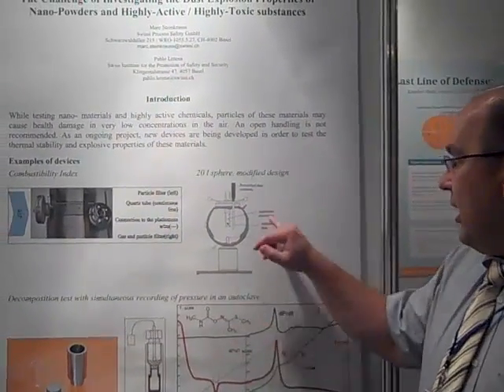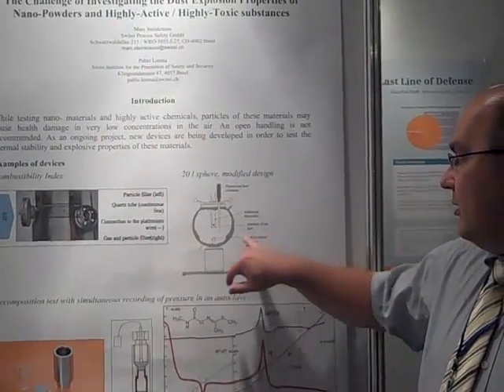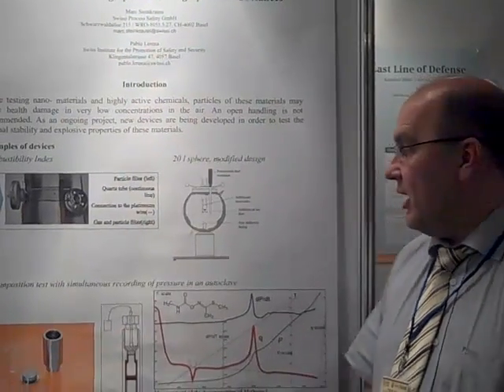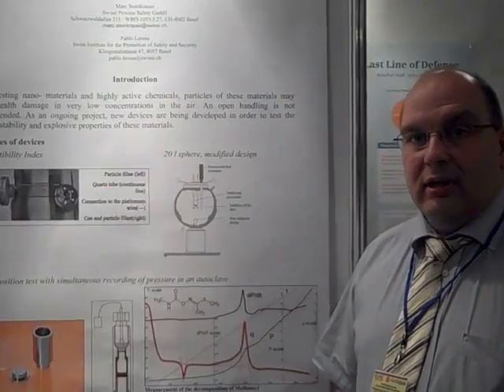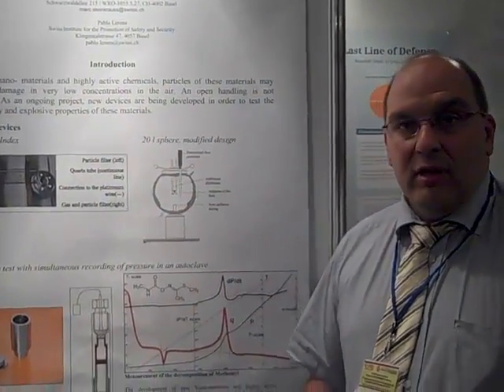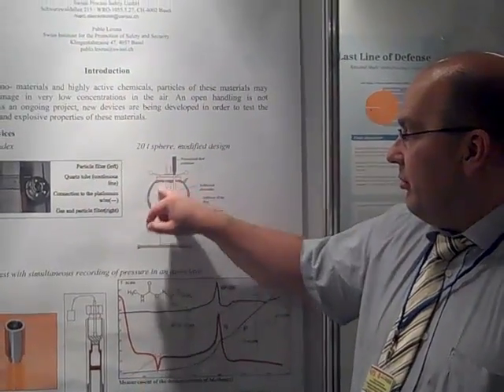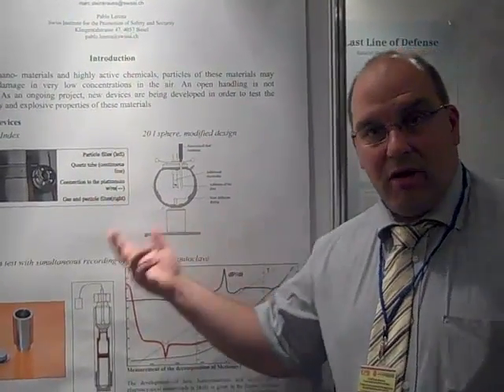For this device we have an additional electrode inside and a new deflector design. This we need after the test to ignite a second substance, for example ethanol. After the test of the powder, we ignite it with gas so the residue of the substance burns out completely.